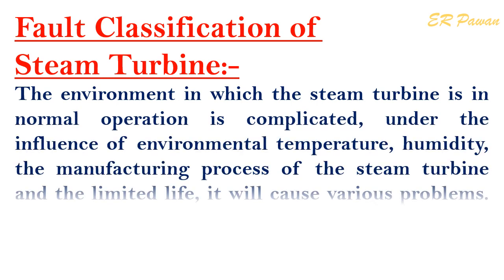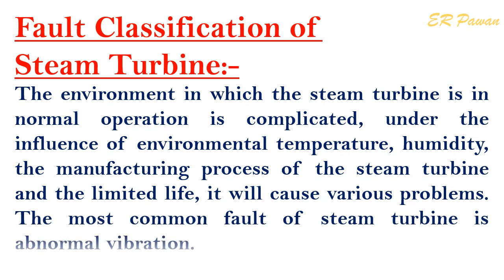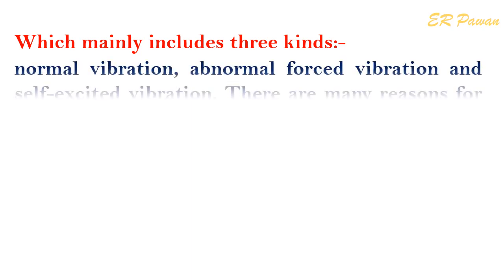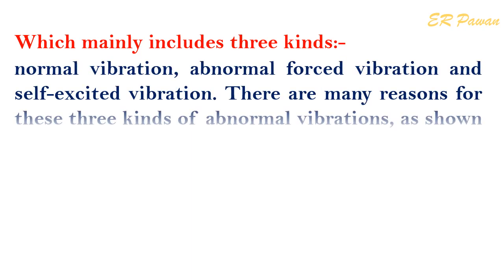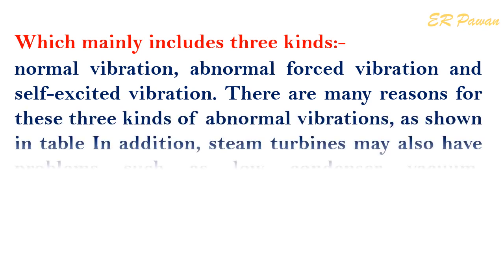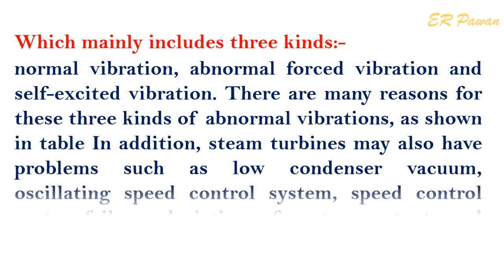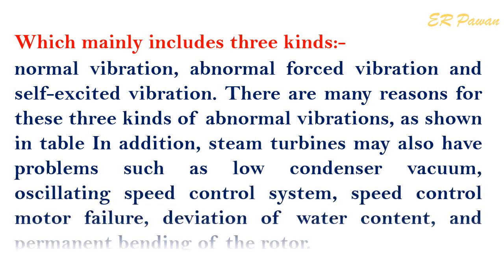Fault classification of steam turbine: The environment in which the steam turbine operates is complicated. Under the influence of environmental temperature, humidity, the manufacturing process, and limited service life, various problems will occur. The most common fault of the steam turbine is abnormal vibration, which mainly includes three kinds: normal vibration, abnormal forced vibration, and self-excited vibration. In addition, steam turbines may also have problems such as low condenser vacuum, oscillating speed control system, speed control motor failure, deviation of water content, and permanent bending of the rotor.